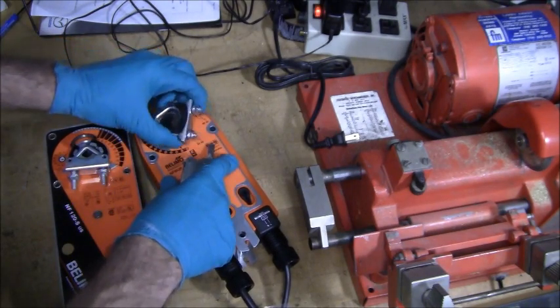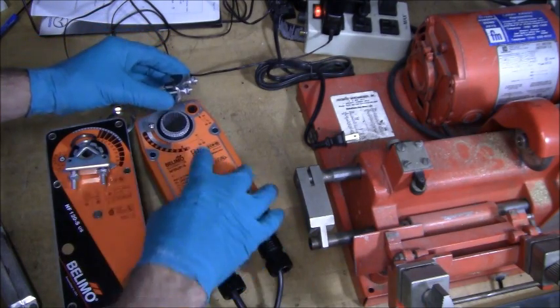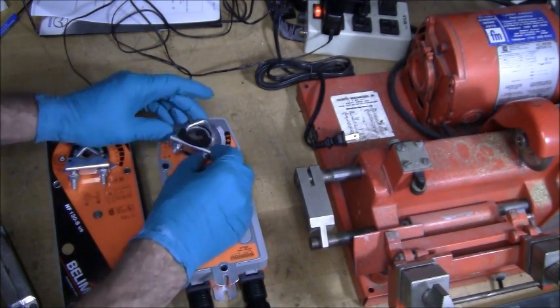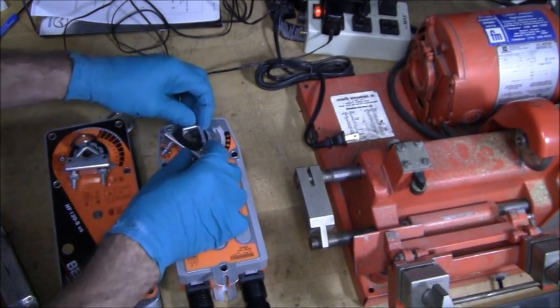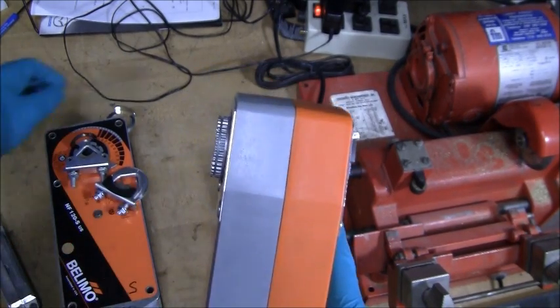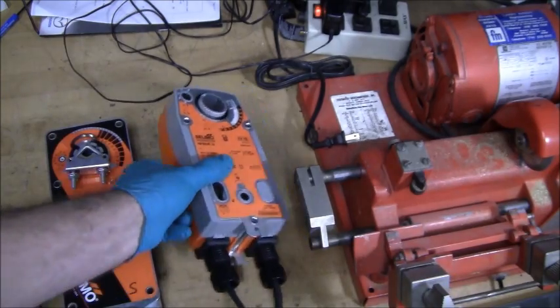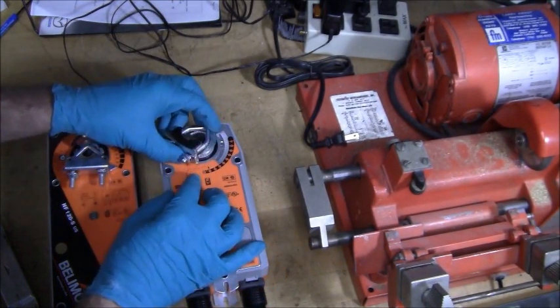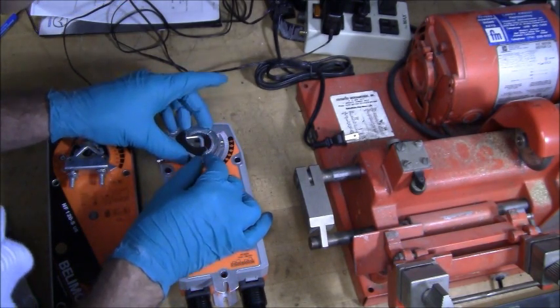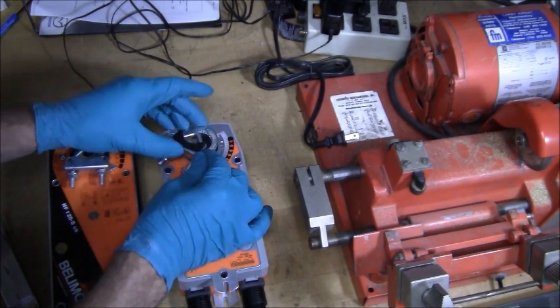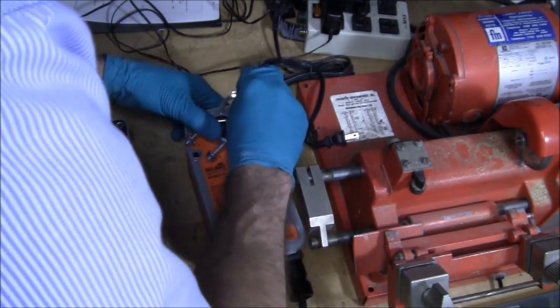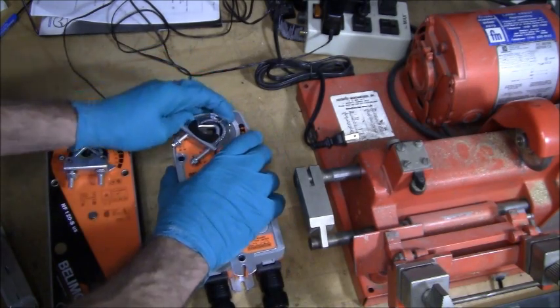This is kind of like a gear here. Now I want to utilize the same direction, which is clockwise. So I'm going to spin that over. Here's the cam, and I want this to be lined up at zero. There is a ring right here which is where this C-clamp goes into once the cam mechanism goes on. Line this up to zero. There's actually a nice mark in the shaft that lines up with this. Now that that's in and pushed down, I can go ahead and put on this clamp. That locks it right in place.